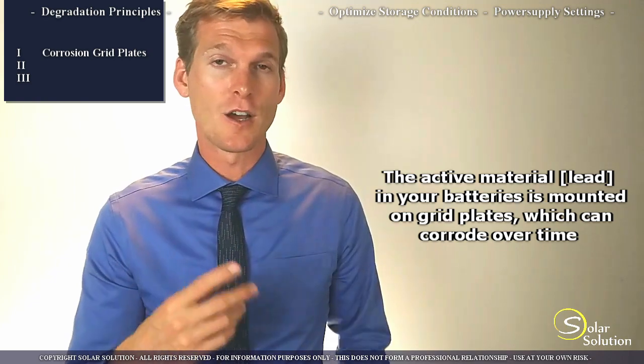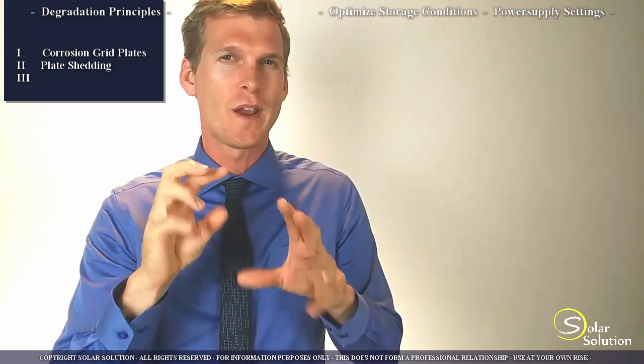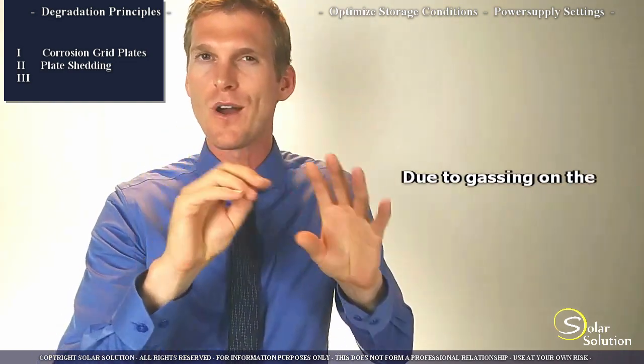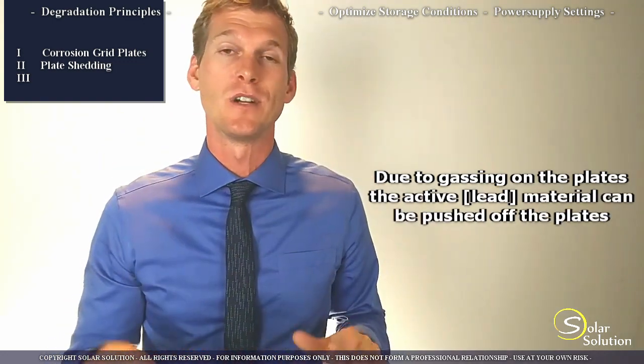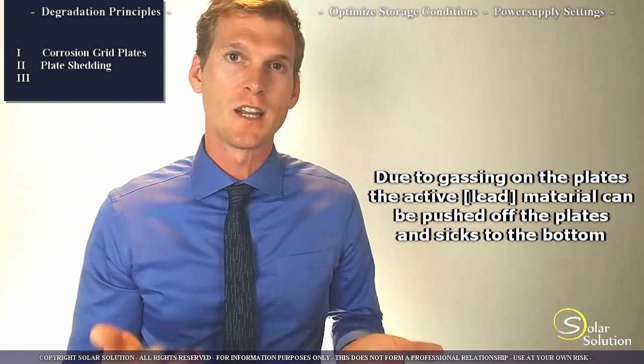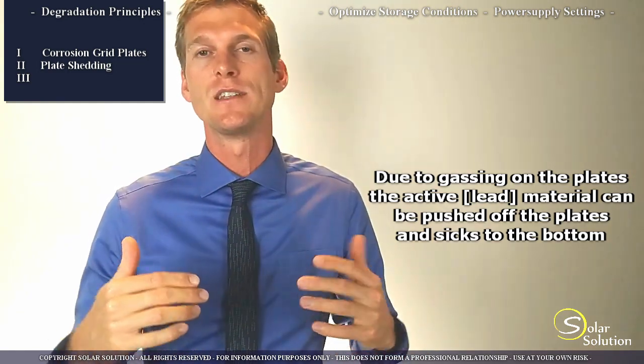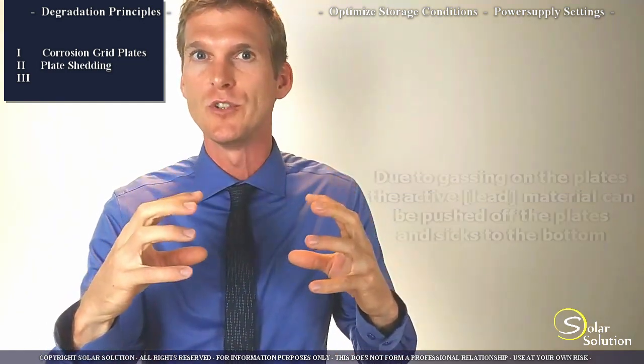The second thing that often happens in batteries is shedding of the active material. So what this means is that during the charging as the battery reaches the end of a charging cycle so the battery is almost full, small air bubbles are being created on the lead plates and these air bubbles then push off part of the lead. This lead falls down to the bottom of the battery where it's no use to us anymore. It cannot be reclaimed and the result is that the capacity of your battery slowly reduces over time.